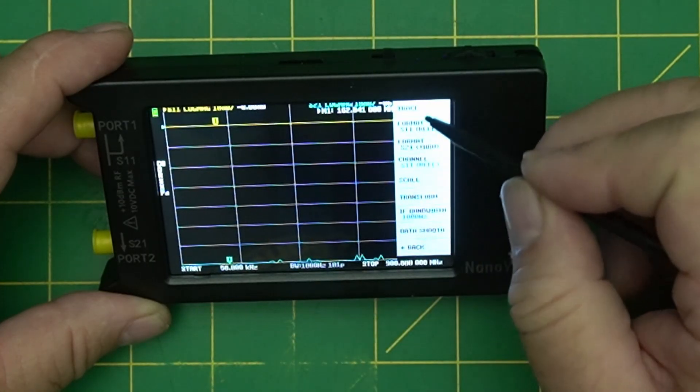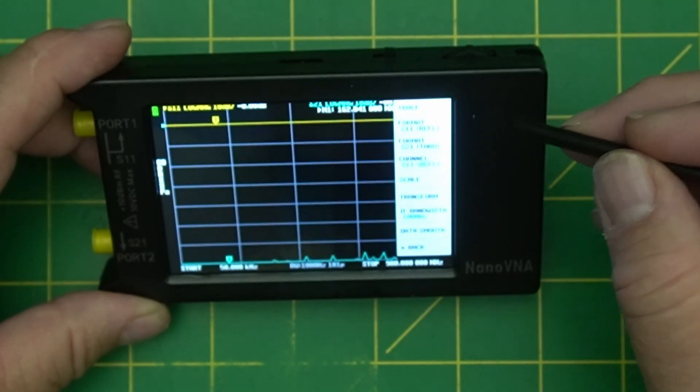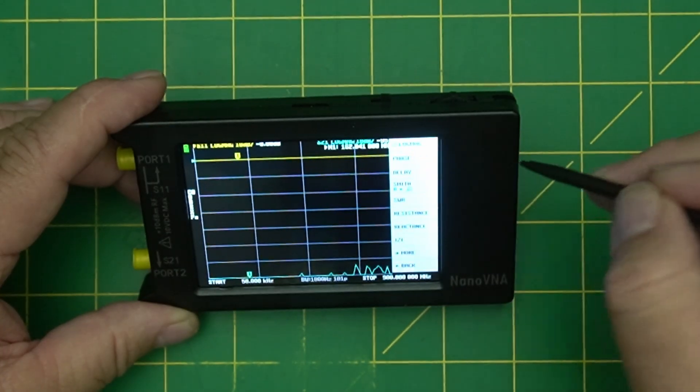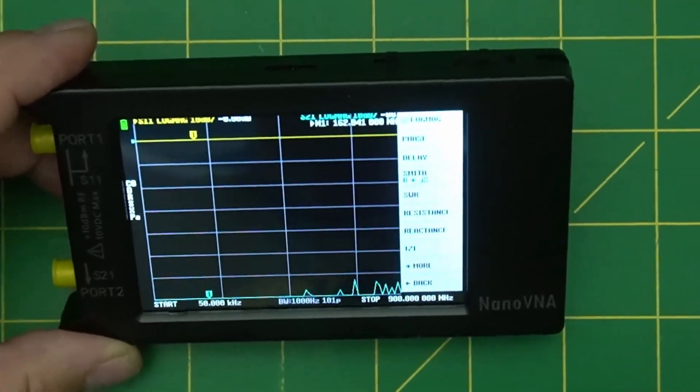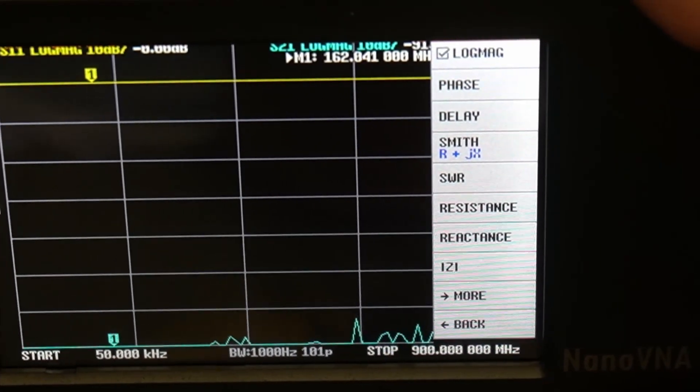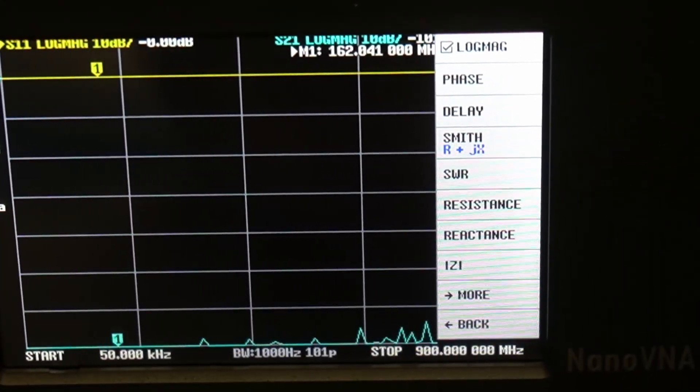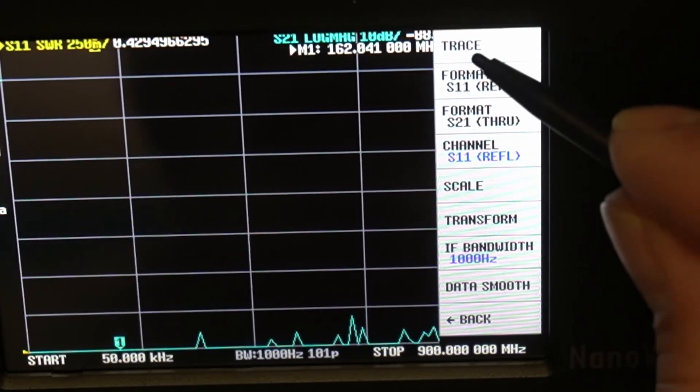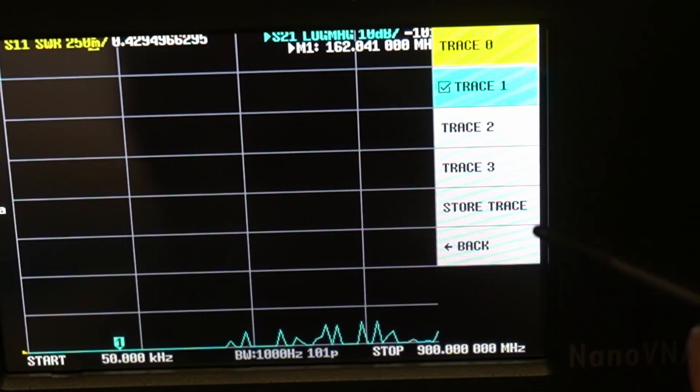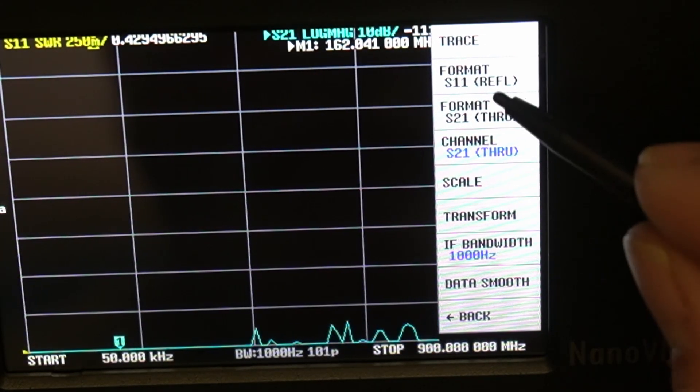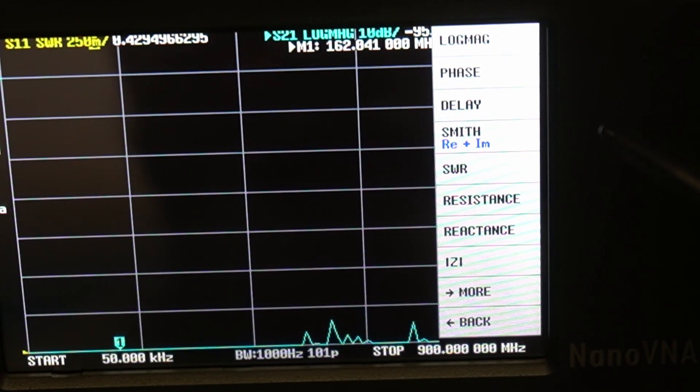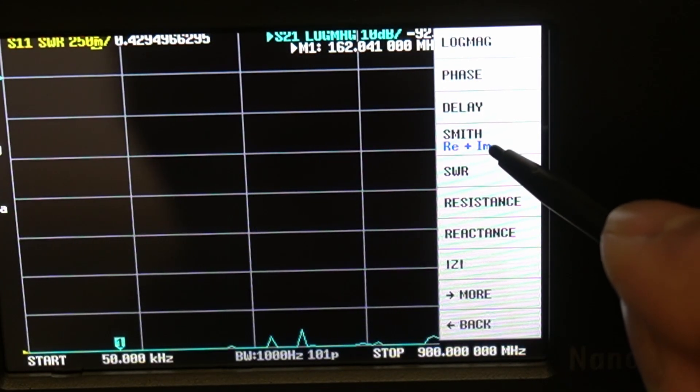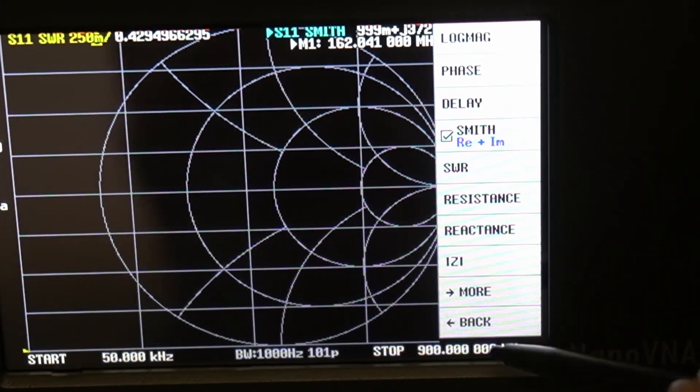Okay. But we're going to back out. Actually, we're going to go back to trace. We're going to, okay, we're on that one. We're going to go back out. We are going to hit, I believe format. And you can see it's on log mag right now. I can bring you guys a little closer. Okay. It's a little dark, but I think you can see the screen better now. So we're going to change the yellow one, which is the one we're on. We're going to change that to SWR. I'm going to go back. We're going to go back to trace. I'm going to go to this trace. It's on. We're going to go back and then we're going to hit format. And that's the 11, not the 21. And we're going to hit Smith chart. There we go. There's Smith chart. So I'm going to leave that on and then we're going to back out.